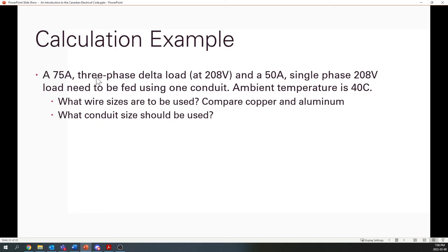This is an example where you have two different circuits in one conduit. I did that so we can actually apply some of the derating factors, the correction factors. So you have a 75 amp three-phase delta load at 208 volts and a 50 amp single-phase 208 volt load. So it's picking off two of the phases. And that needs to be fed using one conduit. And the ambient temperature is 40 degrees Celsius.